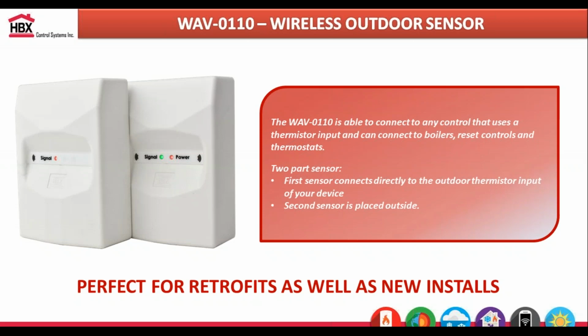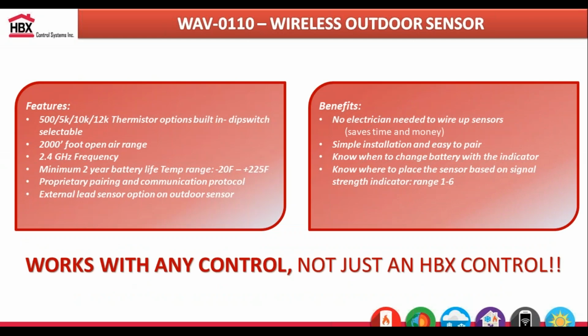So there's a base unit and an outdoor unit. The base unit, you just wire into the thermistor input of your boiler or your heat pump. Your outdoor sensor just runs off 2 AA batteries. You pair the outdoor unit to the base unit in your mechanical room, and you have about 2,000 feet of communication between the base unit and the outdoor unit.